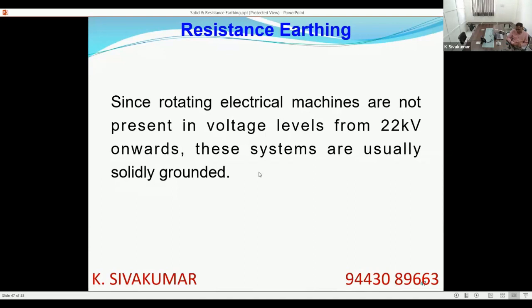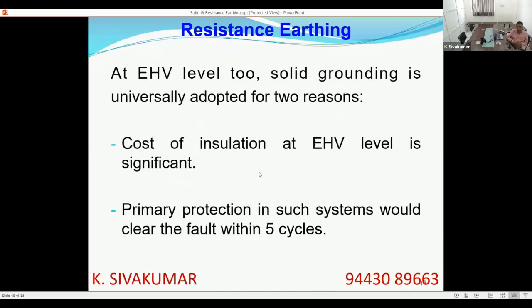If rotating machines are present in the system, you go for resistance earthing. If the rotating machines are not present, you go for solid earthing to gain the advantages of solid earthing. The biggest disadvantage of solid earthing is the core damage curve, but if you don't have rotating electrical machines, you need not worry much about that. But if you have rotating electrical machines, you must go for resistance earthing. At EHV level, beyond 66 kV, solid grounding is adopted.